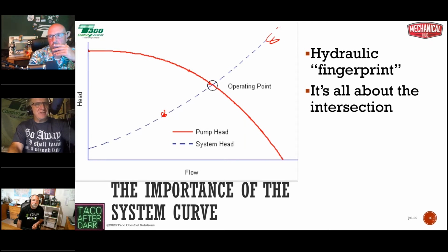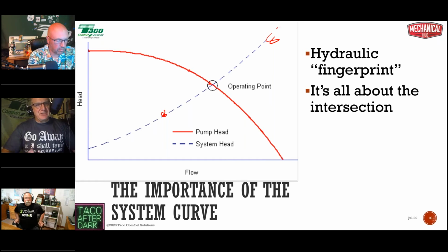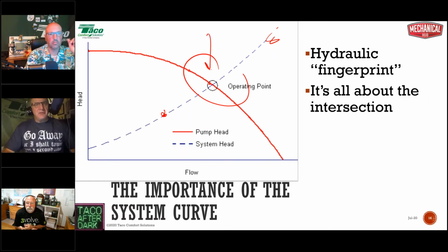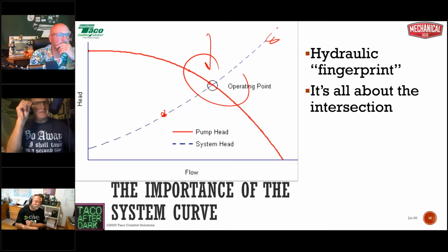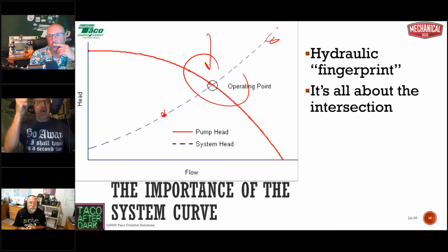As flow increases in a piping circuit, the pressure loss through that piping circuit increases exponentially, all right? So it's not a straight line. As flow goes up, head shoots up, all right? And the only reason we care about the system curve is it's all about the intersection. The system will operate where the system curve intersects the pump curve. Always, always, always. It doesn't matter what kind of pump we're talking about, who makes it, or whether it's a variable speed pump or a fixed speed pump or a 3-speed pump. The system will always work where the system curve intersects the pump performance curve.